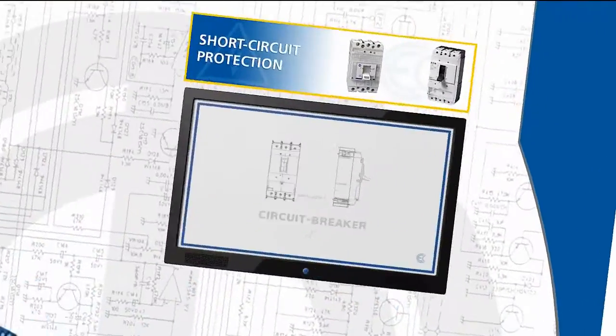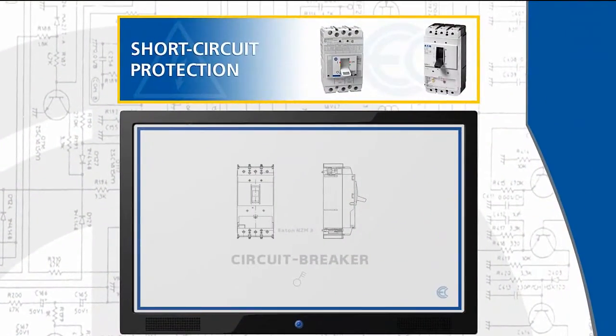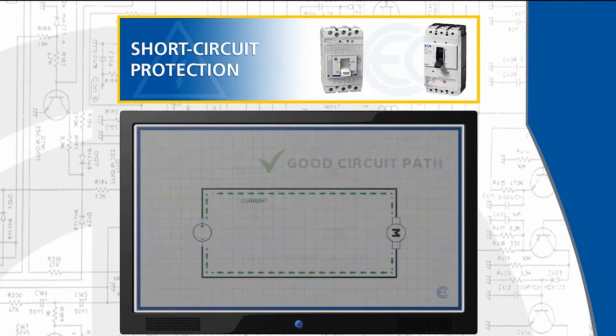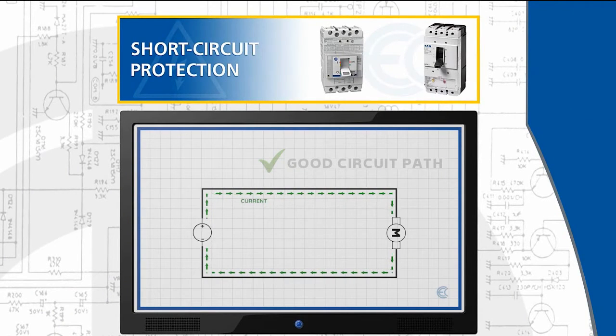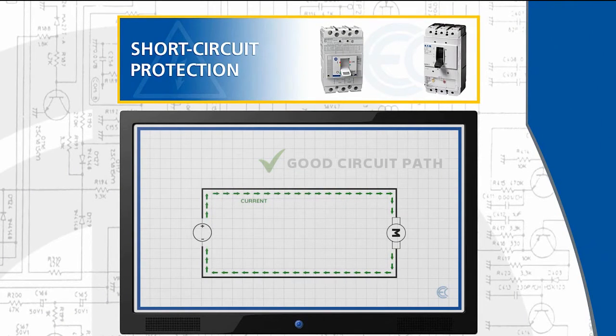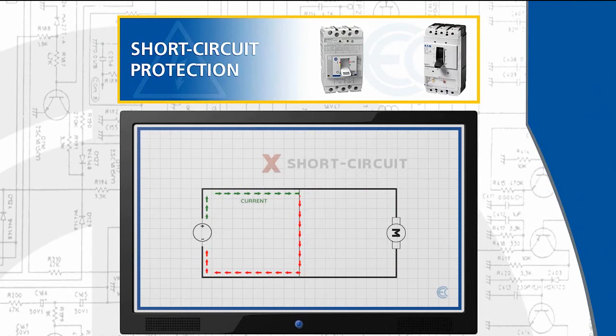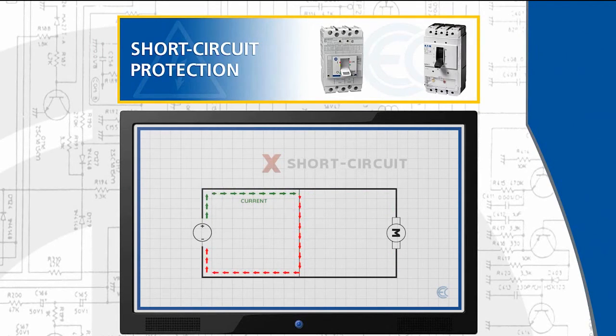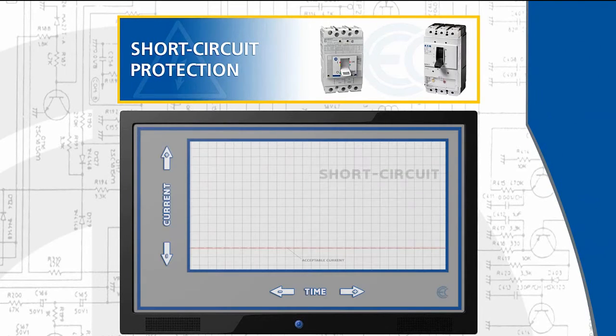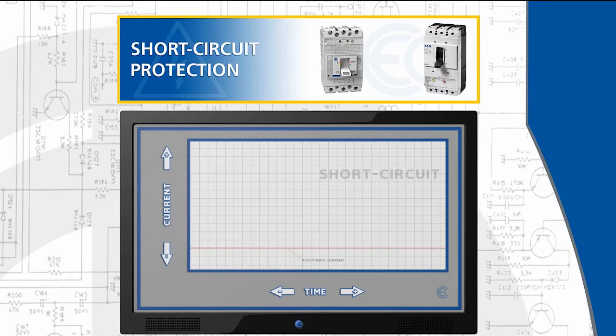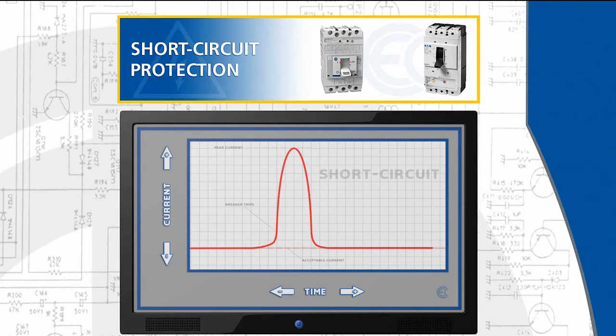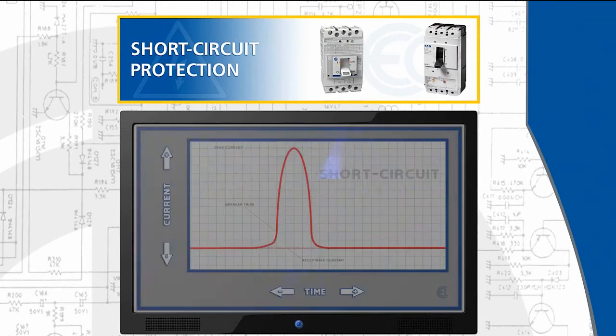Now on the other hand, we have short circuit protection. A short circuit occurs when current travels along an unintended path, often where essentially no or a very low electrical impedance is encountered. Short circuit protection is protection against excessive currents or current beyond the acceptable current rating of equipment, and it operates instantly. As soon as an overcurrent is detected, the device trips and breaks the circuit.